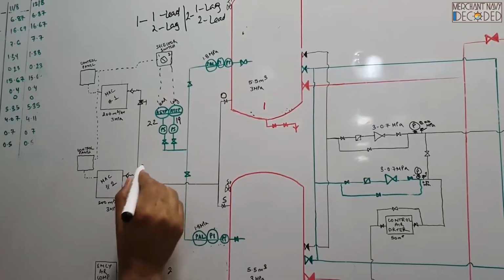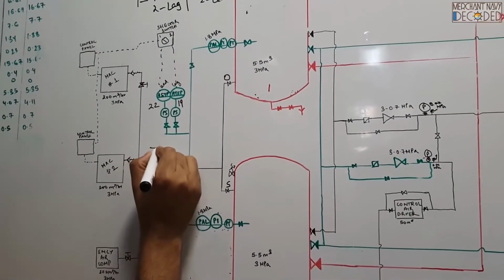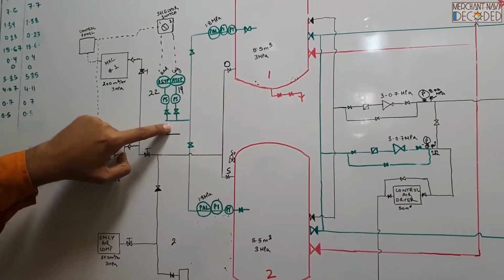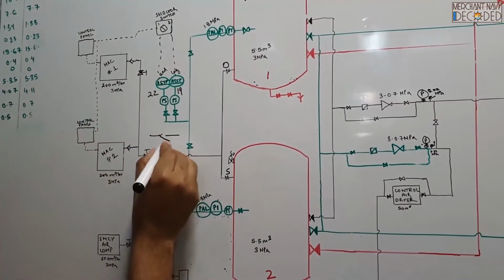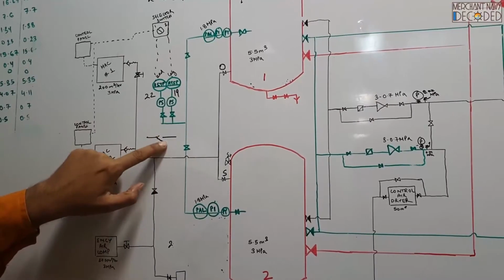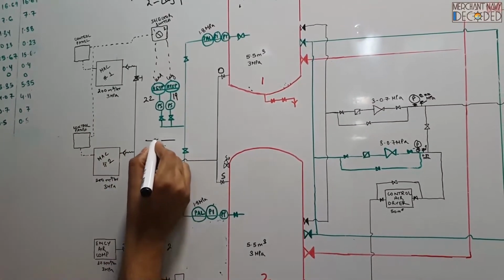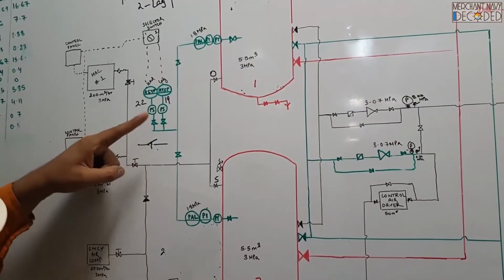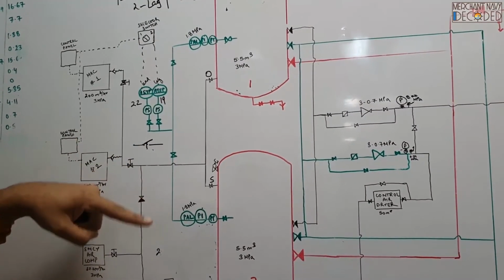And these pressure switches are like these guys. Make or break type. Always pressure switch like make or break. So what happens is, this pressure switch is fitted like this, suppose. Rather, I would make it like this, and there's a spring over here. So when the pressure drops, this is attached with a spring, it comes down and makes contact.